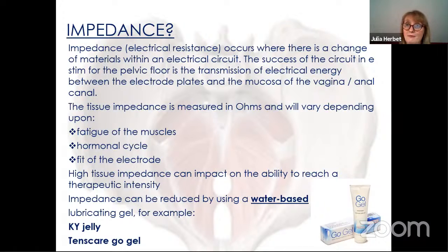And then the other big important thing is the fit of the electrodes. So you'll see when we look at the electrodes, they come in different diameters. So making sure that the electrode is the best fit, the best size for that particular individual is really important, and that will have a huge impact on the impedance. So we can help with the impedance by using a water-based lubricating gel. So KY jelly is a well-known one, but TensCare have their own that people can buy with their devices. So the TensCare Go gel would have that effect as a water-based gel.